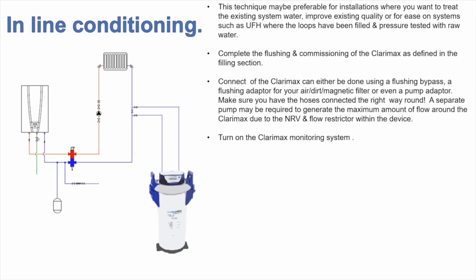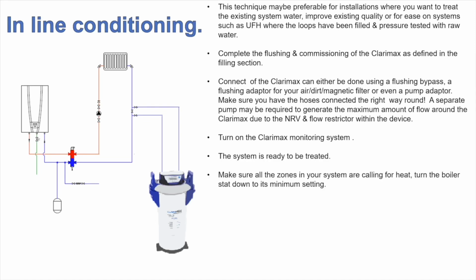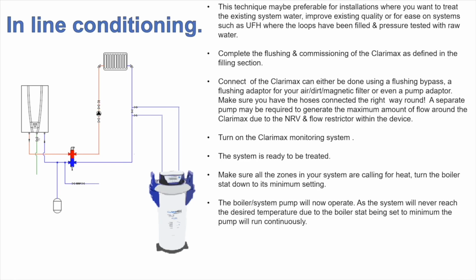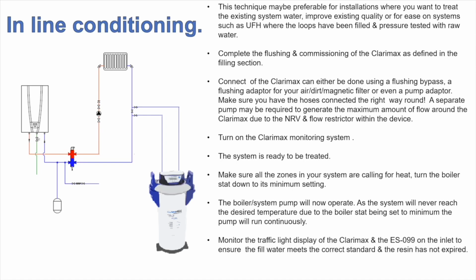Turn on the Clarimax monitoring system. The system is ready to be treated. Make sure all the zones in your system are calling for heat. Turn the boiler stat down to its minimum setting. The boiler system pump will now operate. As the system will never reach the desired temperature due to the boiler stat being set to a minimum, the pump will run continuously. Monitor the traffic light display on the Clarimax and the ES-099 meter on the inlet to ensure the fill water meets the correct standard and the resin has not expired.